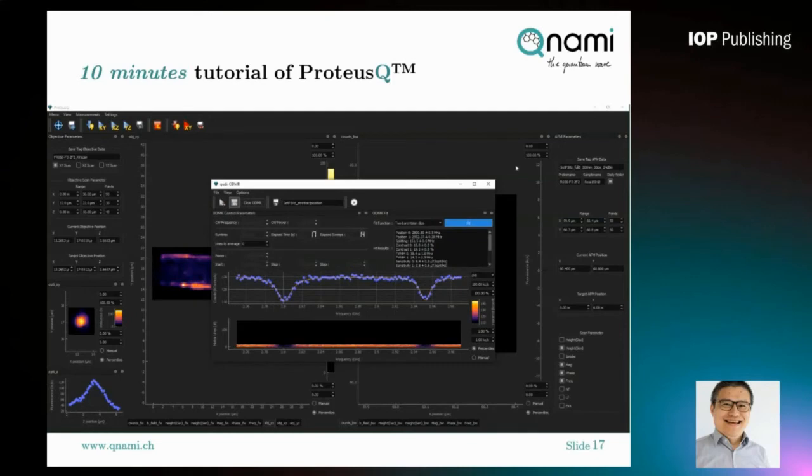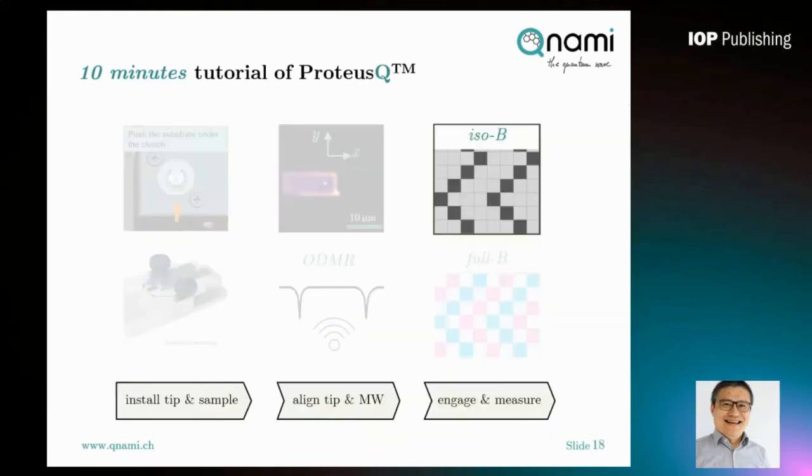The software has an internal embedded fitting function — here we use a double Lorentzian fit. The depth of the ODMR dip is called contrast, and it is an important parameter to ensure you have enough sensitivity. The typical contrast achievable with ProteusQ is 15 to 25%, which is good enough to perform all ODMR-based measurements in the scanning NV magnetometer. We have now finished preparation of tip and microwave antenna alignment.